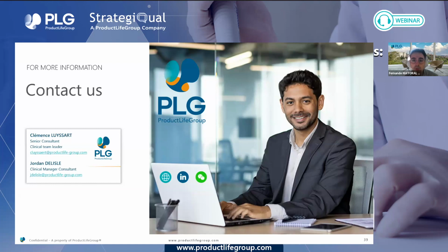Can peer-reviewed literature be used to justify non-clinical studies required by manufacturers with real patient samples? And then she has modified the question and said, for established devices from the IVDD. I'm not sure if it's clear enough, Jordan, Clemens. Yes, it's clear. Thank you. Okay. So the answer is yes.